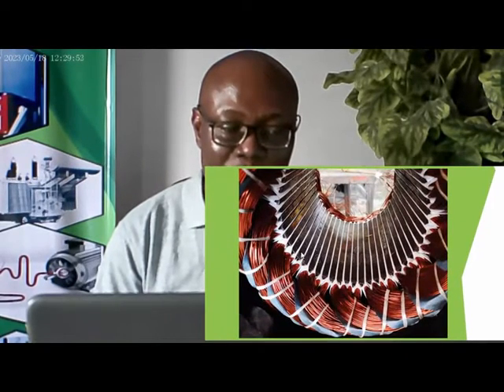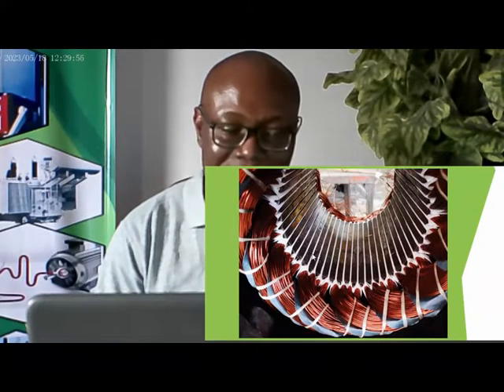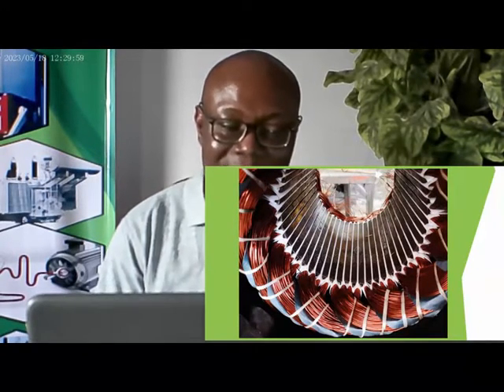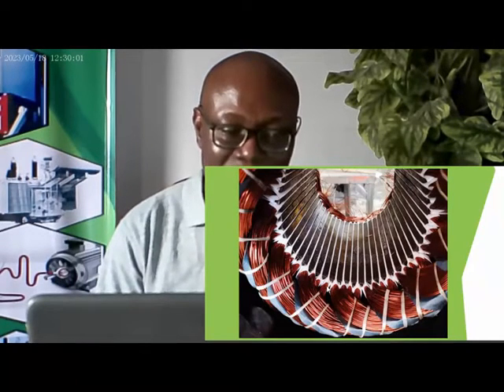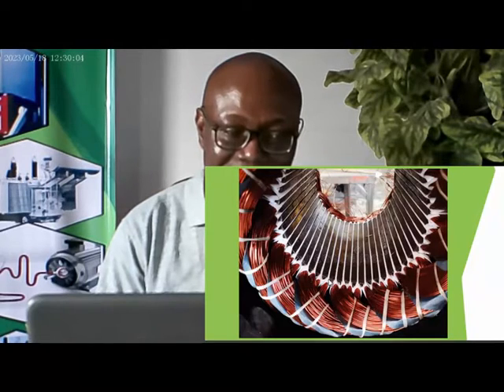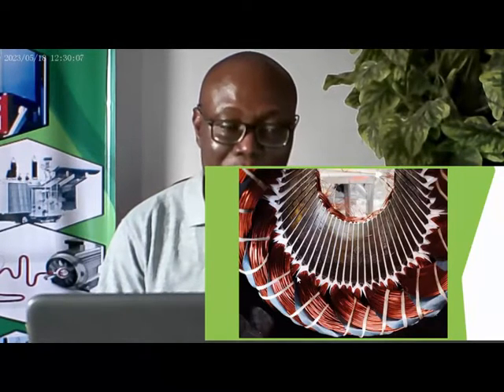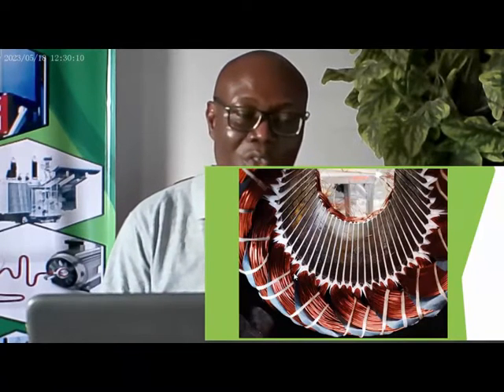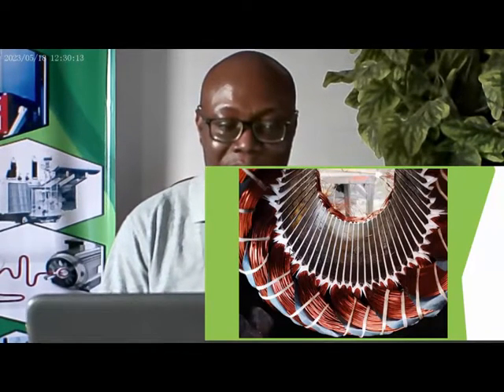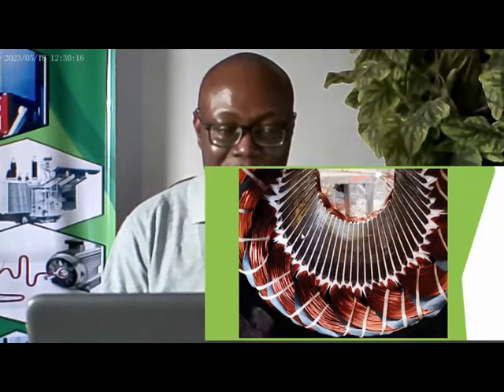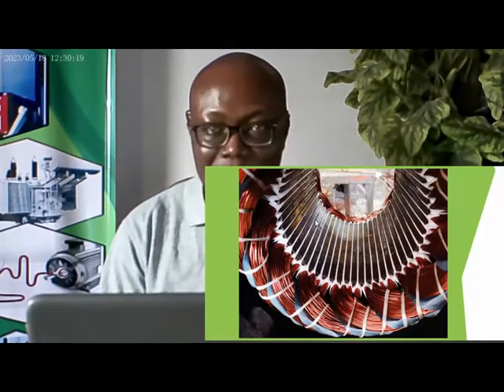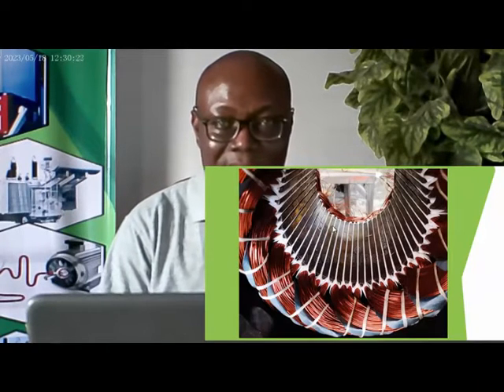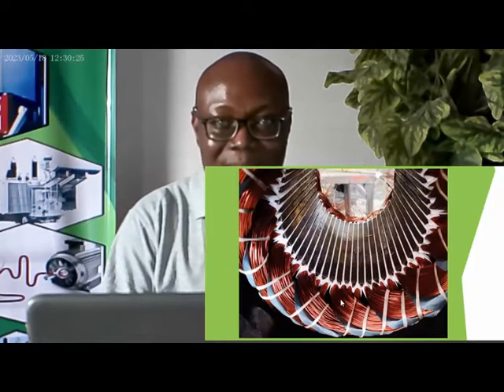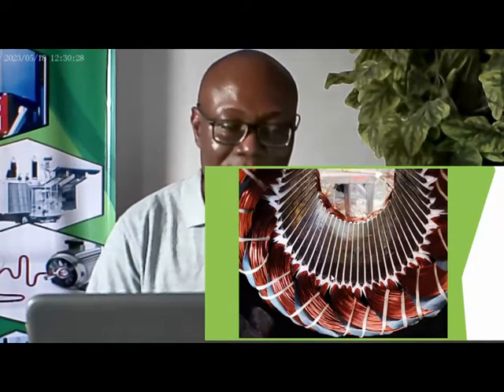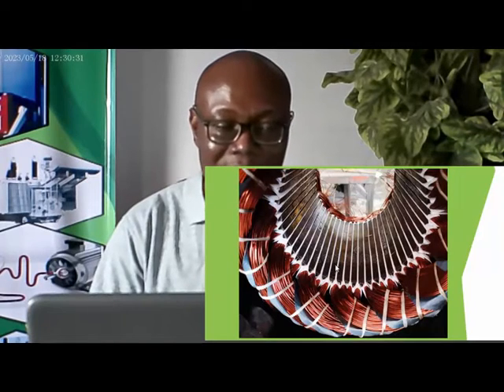If you look very well, you will see that these windings, these coils, are not placed directly on the stator. There is an insulation placed inside the slot before the winding is placed. After placing the winding, another insulator is used to cover the winding within the slot. So this shows clearly that the winding is separated completely from the stator yoke, that is, separated completely from ground.